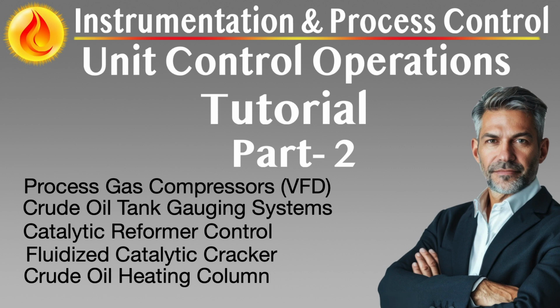Looking ahead, digital twin models of crude heating columns are being deployed in cloud and edge environments. These twins replicate vapor-liquid equilibrium behavior, flashpoint prediction, and energy balances based on real-time sensor inputs and historical data. They enable predictive control, adjusting column set points in advance of expected feed changes or shutdowns. When coupled with AI-based pattern recognition and refinery-wide optimization platforms, the heating column transitions from a passive intermediary to a proactive control node that enhances CDU flexibility, reduces energy intensity, and maintains operational resilience across a wide range of crude blends.